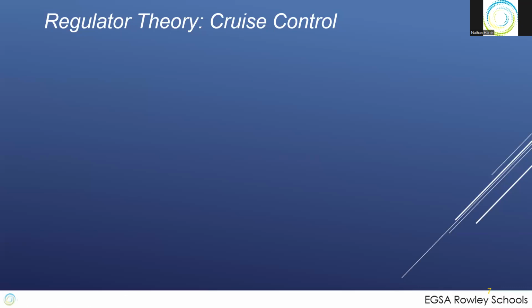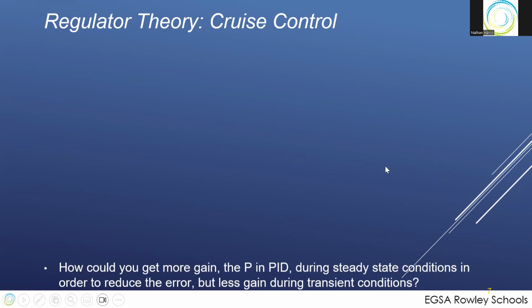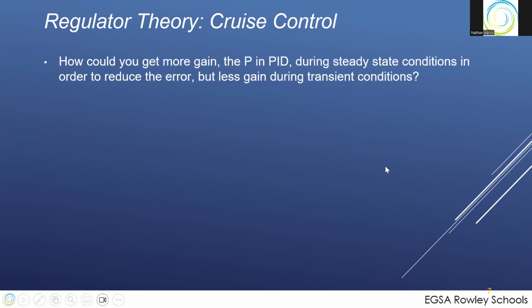So natural resonant frequency is not something you want to have happen very long. And this overshoot we have to control so it doesn't get into this resonant situation. And again, if we could increase more gain so that we could go closer to 60 when we set 60, but when we got into a transient condition, we can reduce the gain, right?